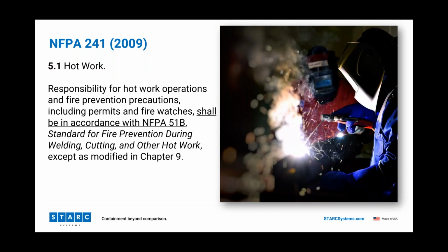So let's dig into some of the specific requirements of 241. So 241 pushes us back from a hot work perspective directly to NFPA 51B. And that's important because in NFPA 51B, this is where we get things such as our hot work permits and some of our fire watch requirements during hot work, and where hot work is permitted in designated areas and non-permissible areas. So it's very important. It's also interesting to see how one code, our chief code 101 life safety code, references something which references additional information. Sometimes you have to follow that lineage to figure out the requirements.